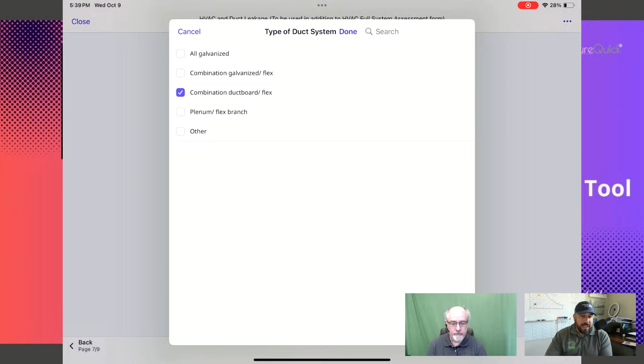One more follow up for you. The duct leakage test gives me total quantitative leakage from wherever, right? Do you also use a pressure pan to try and isolate where your leakage is? I do own a pressure pan, and if I see some really bad numbers, then I'm going to do some further diagnostics there, and I probably need to build that into my process. It's more something that I'm probably just putting in the comments section. There isn't a line item on the checklist for that, but I probably should have one.